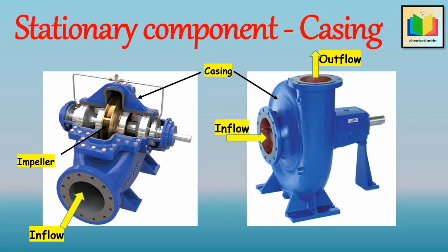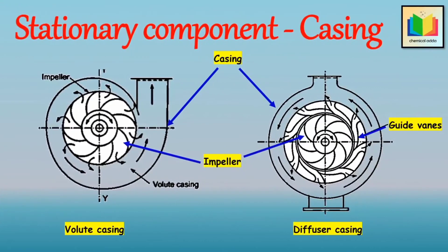Casings can be designed as solid casings or split casings. In a solid casing, the entire casing including the discharge nozzle is contained in one casting or fabricated piece. In a split casing, two or more parts are fastened together. When the casing parts are divided by a horizontal plane, it is described as horizontally split or axially split. When the split is in a vertical plane perpendicular to the rotation axis, it is described as vertically split or radially split. There are three general types of casings: circular casing, volute casing, and diffuser casing.